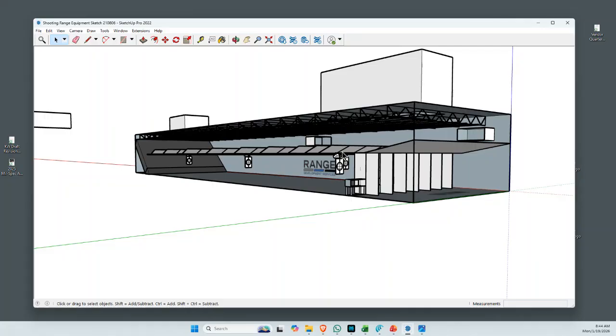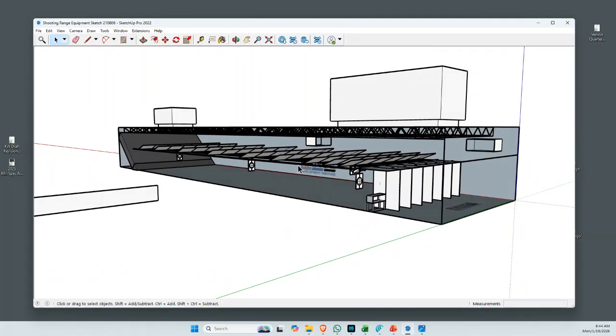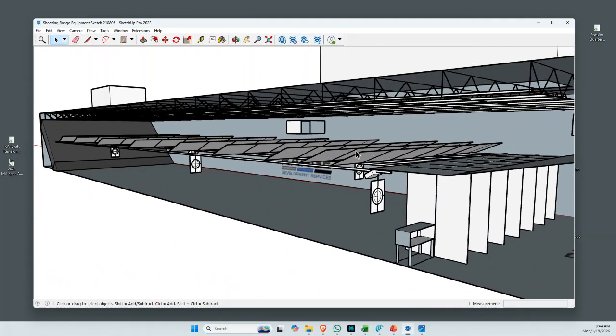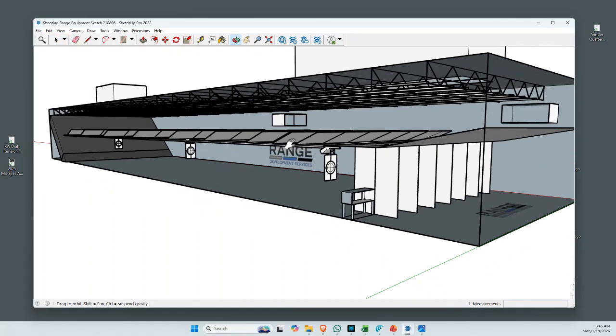We've had ranges big enough to where we had probably a $25,000 budget for a lot of these elements. And so the unistrut and its installation will be on the GC. So that connection can't just be clamped unless the architect and structural say that they can be clamped. Typically, they're going to need to be welded in some form or fashion for structural integrity, because again, each of the 4 corners of these 400 or so pound steel plates connect up, and up. And so you end up with a lot of connections for every single row.